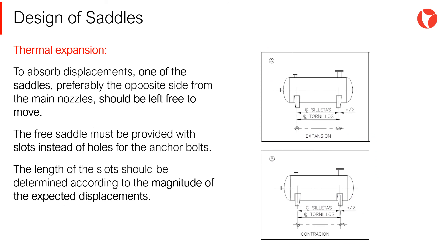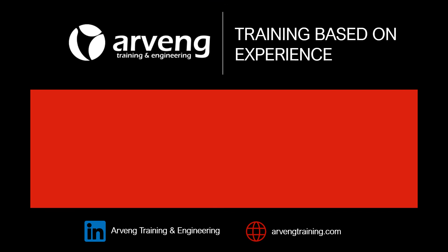A pressure vessel operating at high temperature would suffer thermal expansion. To absorb this displacement, one of the saddles — preferably the one opposite from the main nozzle location — should be left free to move. The free saddle must be provided with slots instead of holes for the anchor bolts. The length of the slots should be determined according to the magnitude of the expected displacements.